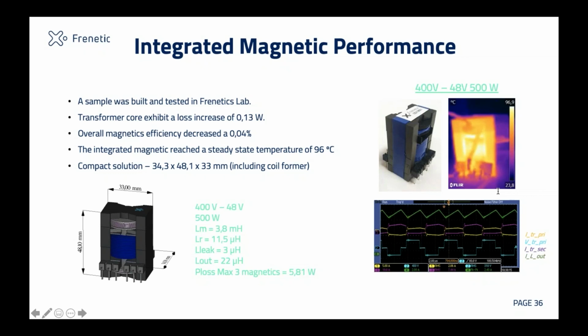How are the copper and core losses calculated, and what wire is used? For the calculation, not measurements, we use Frenetic, which is based on artificial intelligence. The AI is trained on real measurements and analytical models, and these analytical models come from Dowell's equation, Bessel equation, and modified formulas for estimating core losses. Regarding the wire, it's Litz wire, which is very common in this type of transformer. Litz wire is selected to reduce the effects of proximity losses and AC resistance.